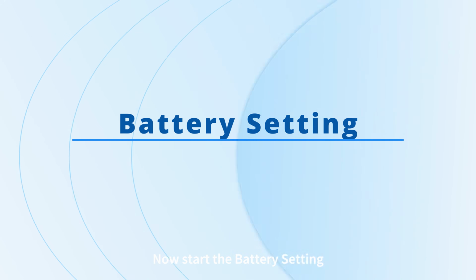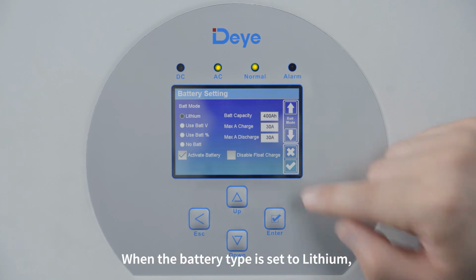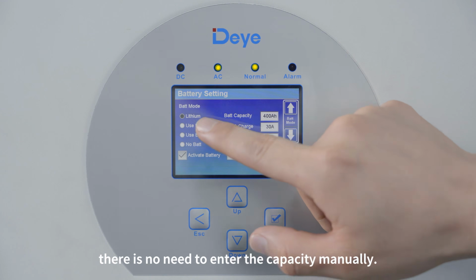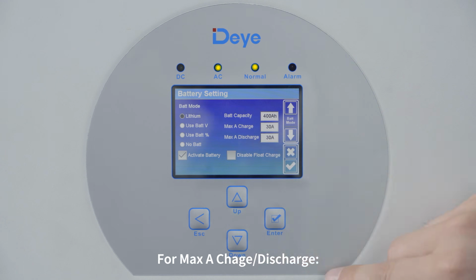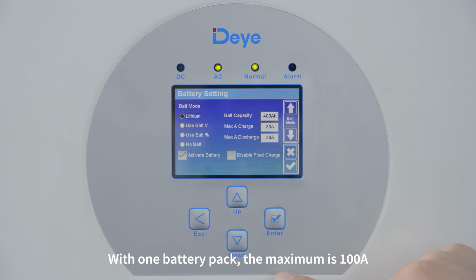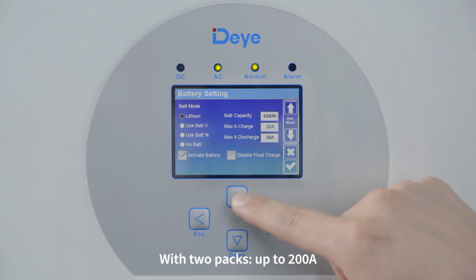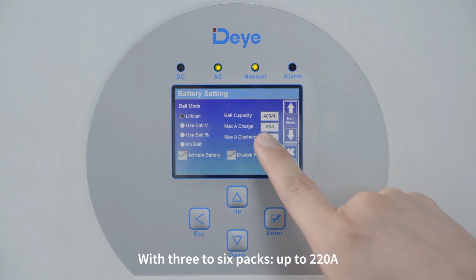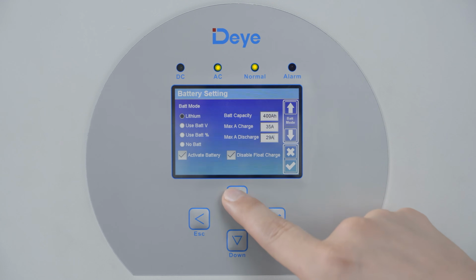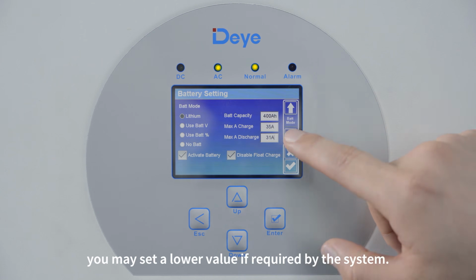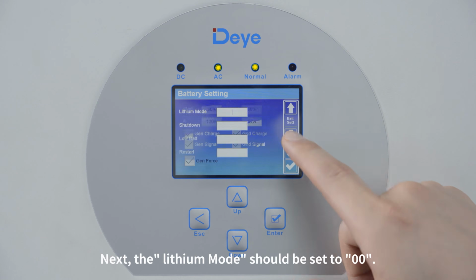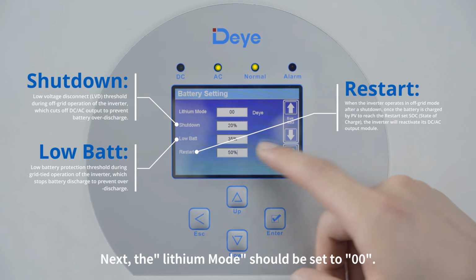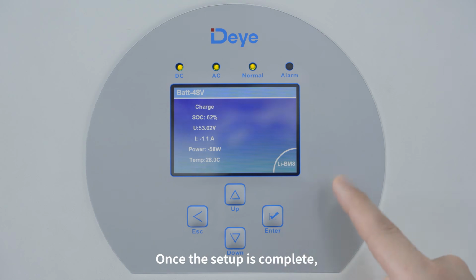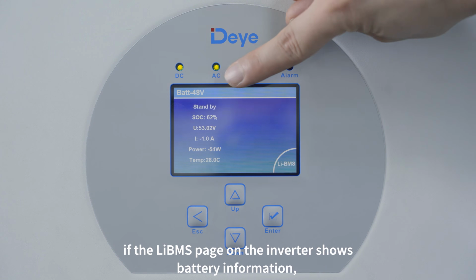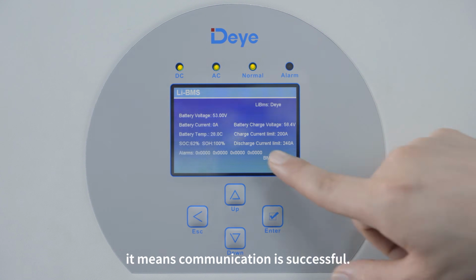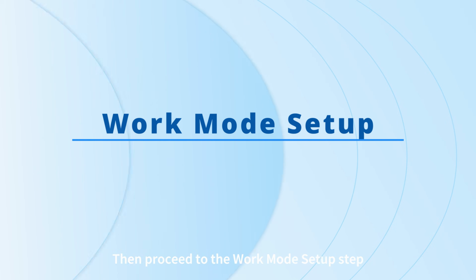Now start the battery setting. When the battery type is set to lithium, there is no need to enter the capacity manually. For max discharge amps, with one battery pack, the maximum is 100 amps, with 2 packs, up to 200 amps. With 3 to 6 packs, up to 220 amps. Of course, you may set a lower value if required by the system. Next, the lithium mode should be set to 00. Once the setup is complete, if the LiBMS page on the inverter shows battery information, it means communication is successful. Then proceed to the work mode setup step.